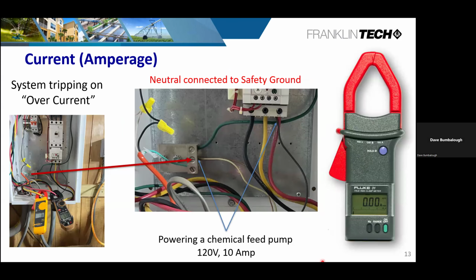Pay attention to the motor manufacturer's recommendations there. They will list what that maximum is. Now, to start our troubleshooting, as we started looking down through this system, the overload protection was tripping. As we started investigating it, as you can see in this picture here, we're checking the motor amp draw, which was correct, but then the overload protection up here was tripping, even though we had the dial set to the correct amperage for that motor. But then we realized here we have a chemical feed pump, and it happens really often where we're borrowing off the power supply, which makes sense because when the contactor closes, it starts both the primary pump and the chemical pump. Well, that's not the correct way of doing it.